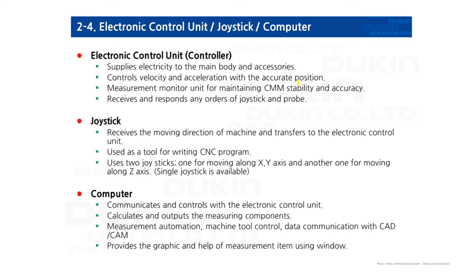Third, the electric control unit, also known as the controller. We usually call it the controller, so don't get confused. On the controller, the power switch is located for turning the machine on and off. The controller supplies electricity to the main body and accessories, and also controls velocity and acceleration with accurate positioning. So this component is in charge of CMM's stability and accuracy.